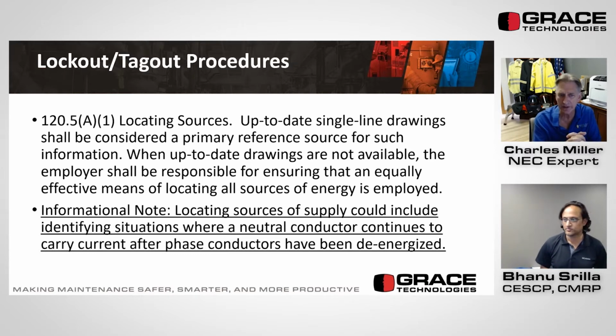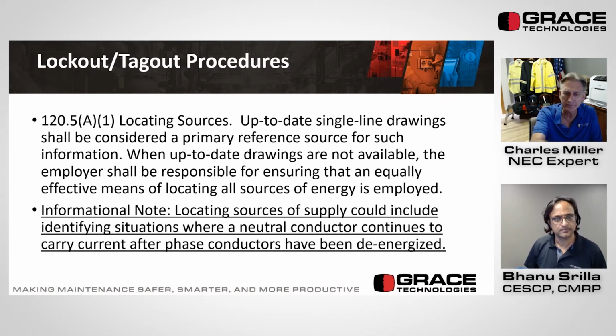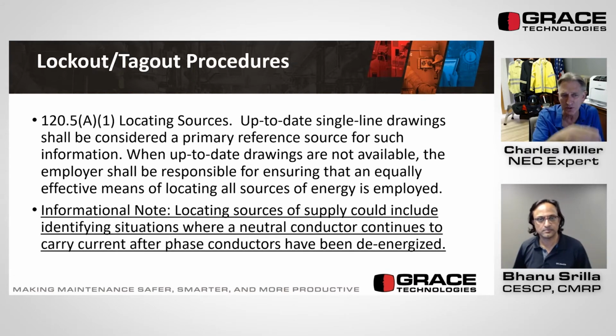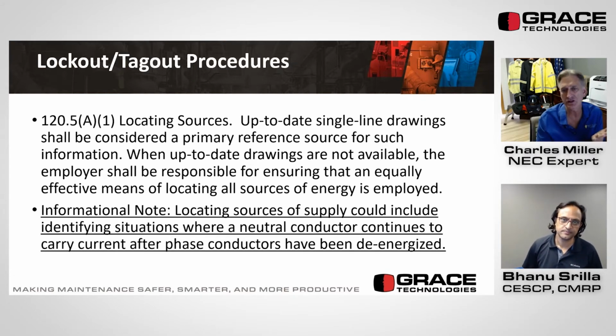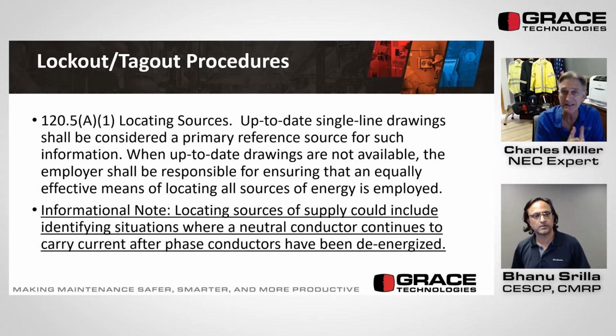using up-to-date line drawings considered as a primary reference. In 120, it didn't have a scope. So where 120.5 is now electrically safe work condition, before it was not. So this may have been 120.4 before. And it's just telling us that up-to-date line drawings have to be considered as a primary source for the information. If up-to-date drawings are not available, employers shall be responsible for making sure that there's an equally effective method for locating all the energy that someone is going to be near or around.